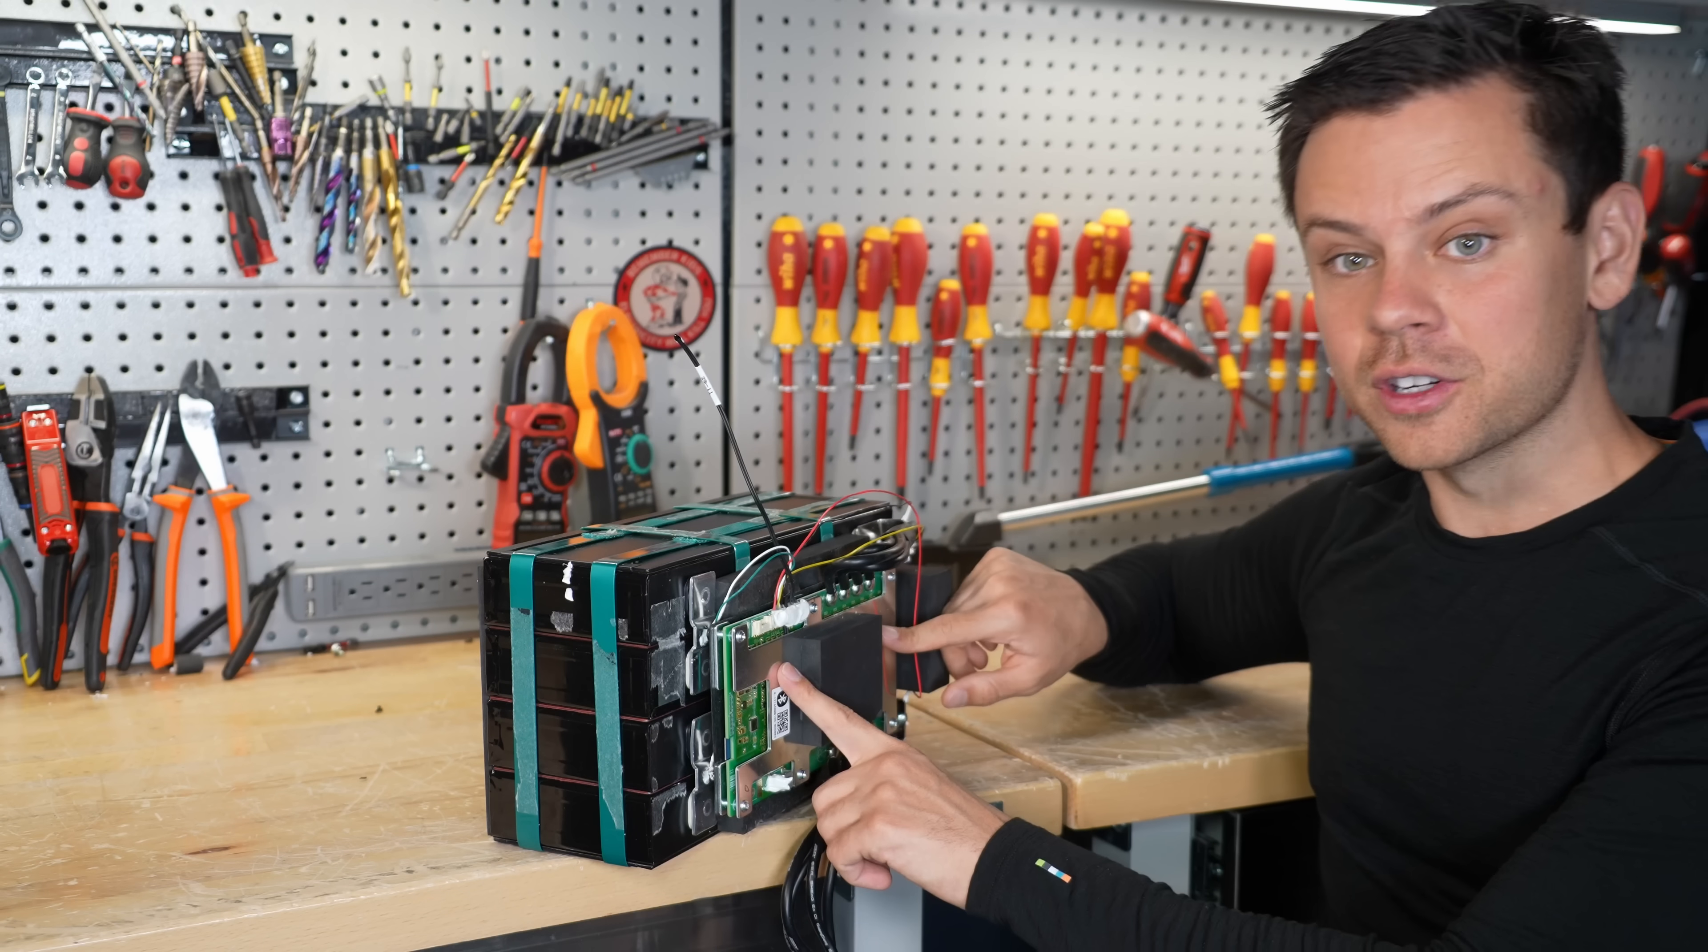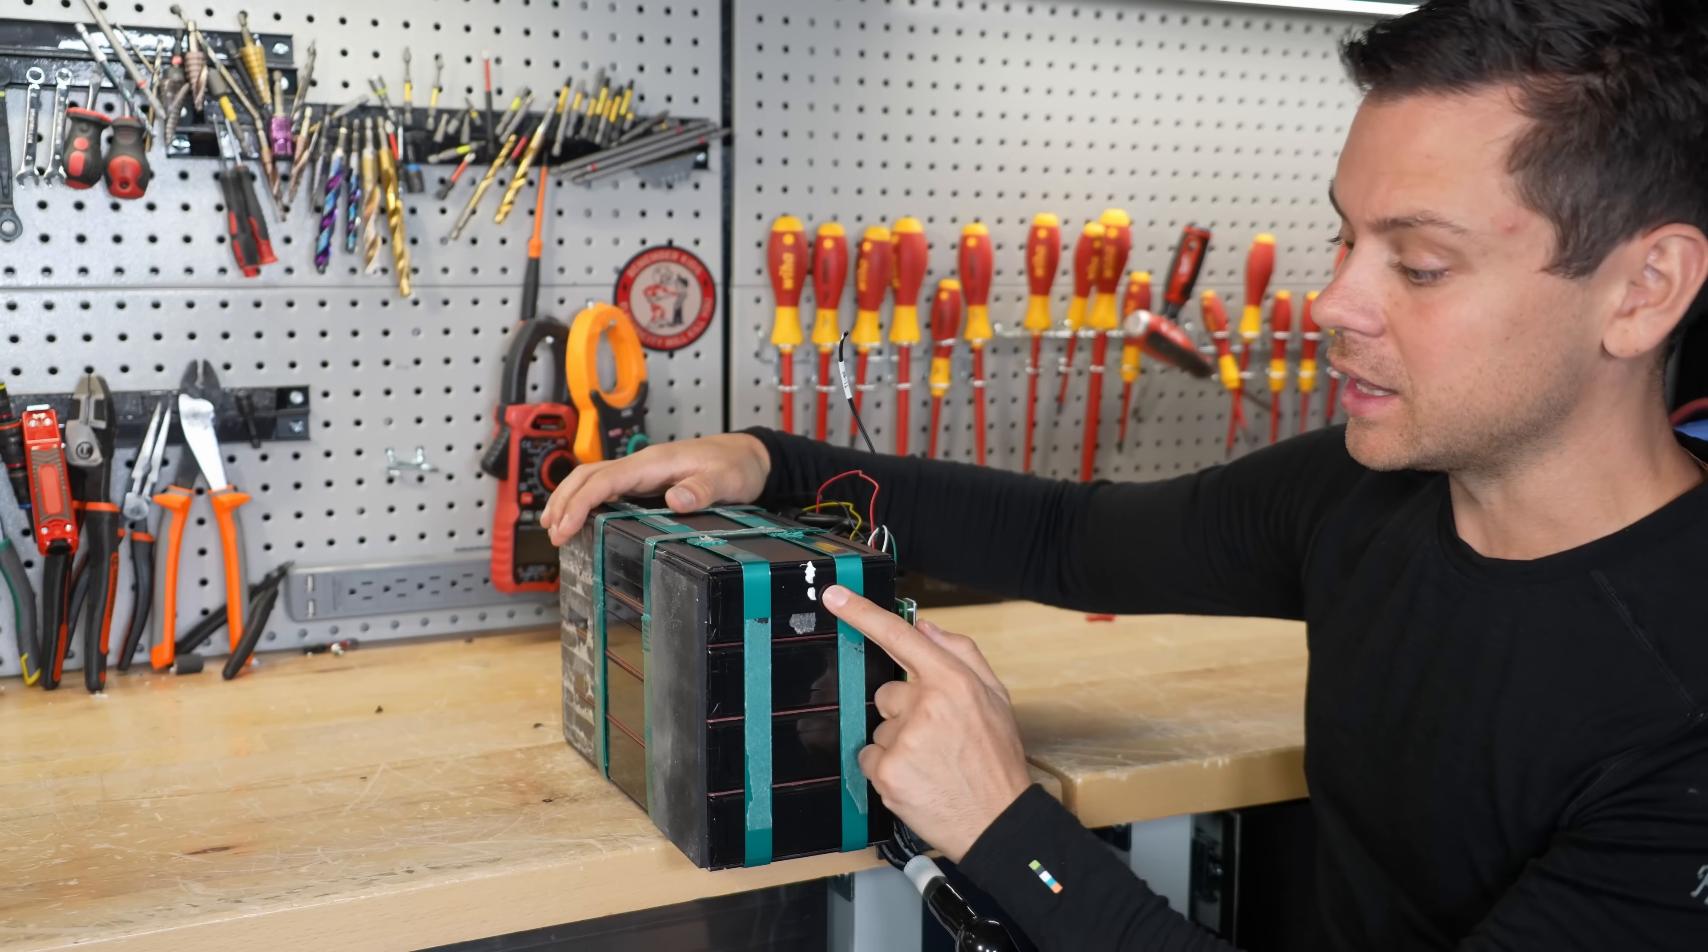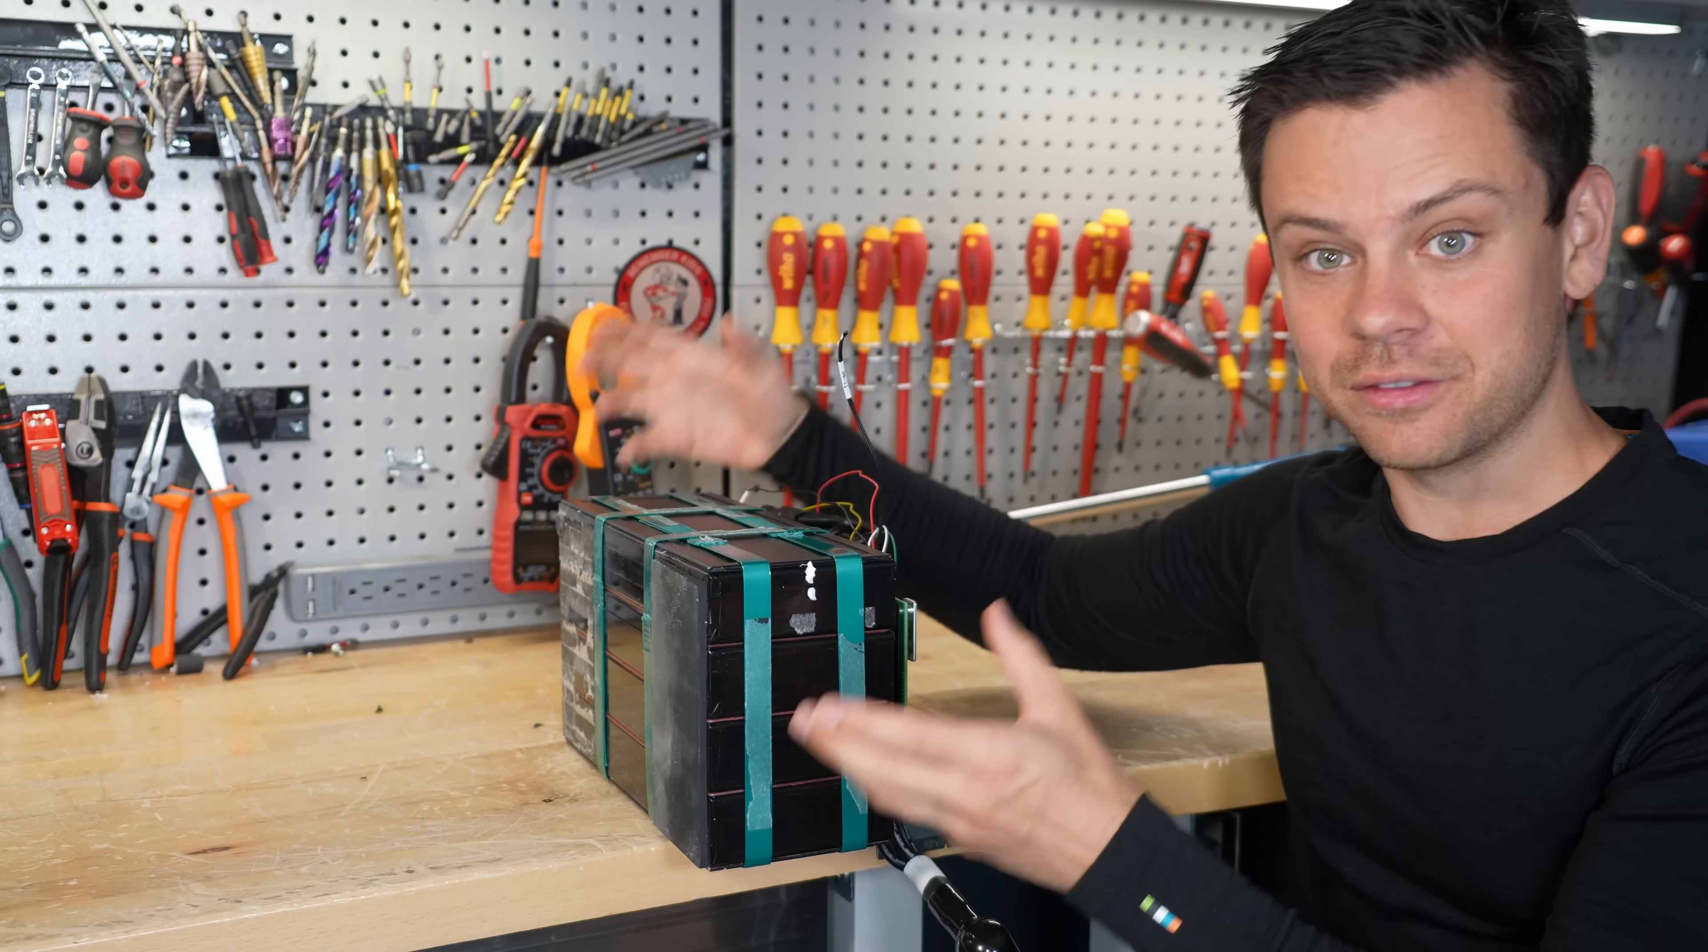Also, if you try to over-discharge this battery or charge it when it's frozen, you can get dendrite formation in the cells. And if it causes a short, if it's any other chemistry, it can literally catch on fire.